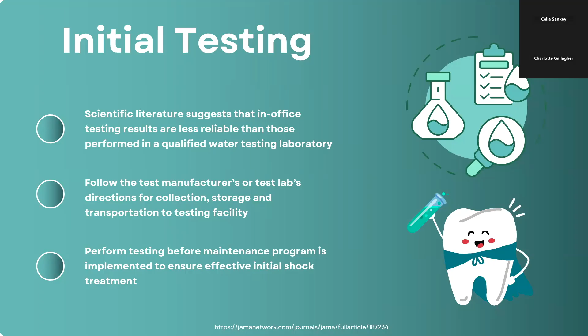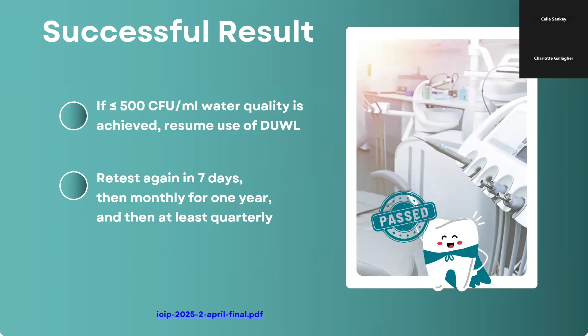You have achieved a successful result if a water quality of less than 500 CFU per milliliter is achieved. You may resume use of the dental unit water lines and retest again in 7 days, then test monthly for 1 year, and then at least quarterly from there on as the water quality is adequately maintained.